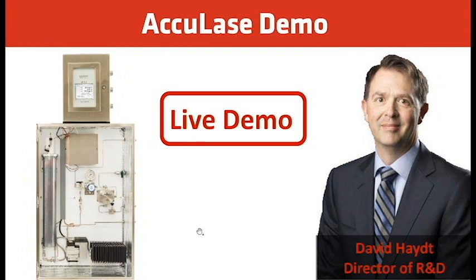Okay. Does the analyzer have to discharge to atmospheric vent? It does not necessarily have to discharge to the atmosphere. We can discharge it to a low pressure flare. We can tolerate up to about 2 or 3 pounds of pressure on the output. Just one thing to bear in mind is that if you're having flare activities where the pressure in the flare line may go up, it can certainly affect, well, two things. You want to make sure you have some kind of mechanism to prevent backflow to the analyzer, so a check valve or something like that. And also, if the pressure in the vent line gets too high, it can affect the readings of the analyzer. Typically, you'll get a false high if there's too much pressure in the vent line.